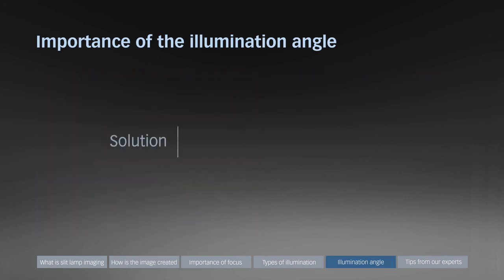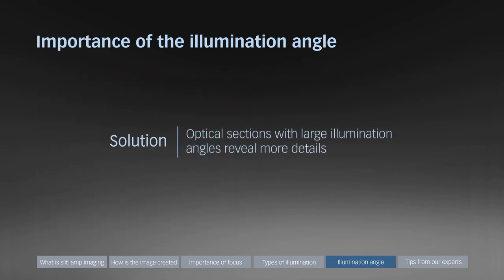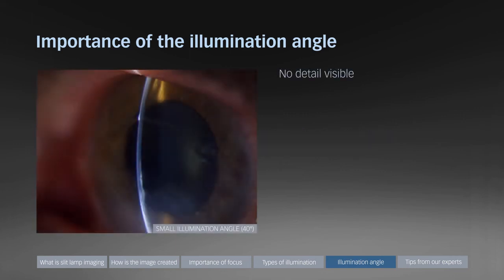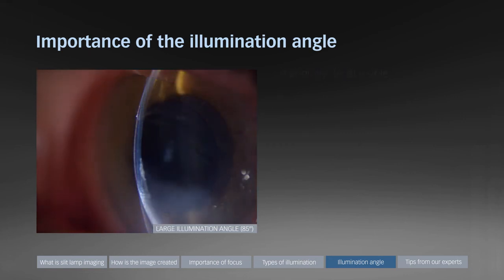The use of a large illumination angle is also beneficial in transparent media. Optical sections with large illumination angles reveal more details and can improve the depth of focus. An image captured with a relatively small illumination angle of about 40 degrees shows some pathology affecting the inferior cornea. The same eye captured with a large illumination angle of about 85 degrees reveals that the inferior cornea is thickened and that there is pathology affecting both anterior and posterior surfaces.